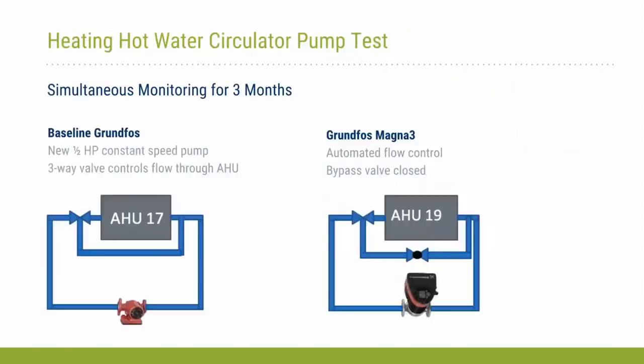Okay, next slide. So the next one that we looked at was the air handling unit evaluation. This one was different than the other one in that we tried to essentially find 2 air handling units that were as identical as possible. And so we have air handling unit number 17 and 19 in building 810, where we did side-by-side testing. So rather than doing before and after testing, we just monitored these in parallel.